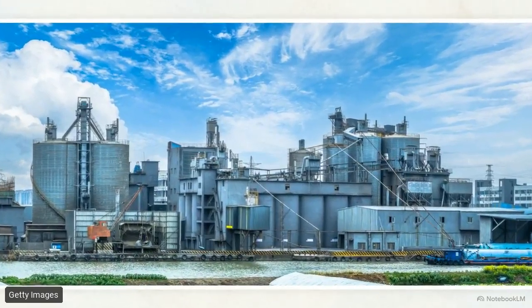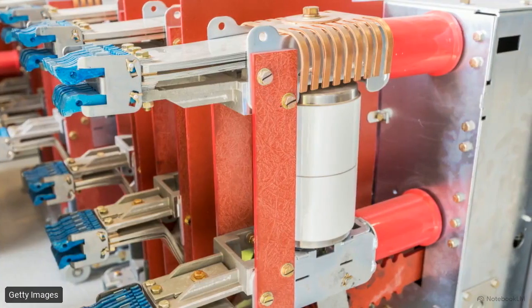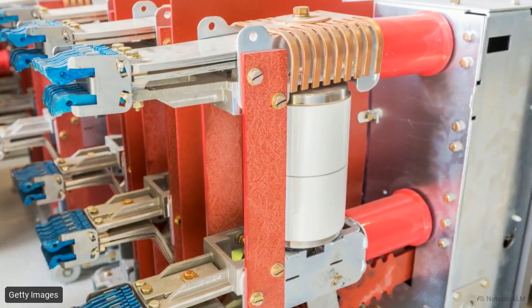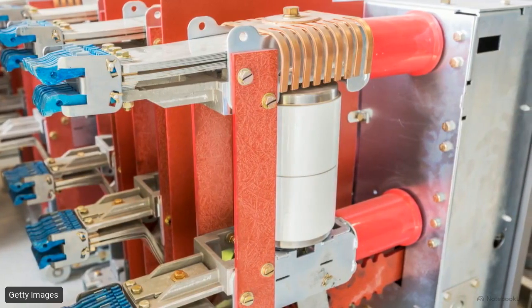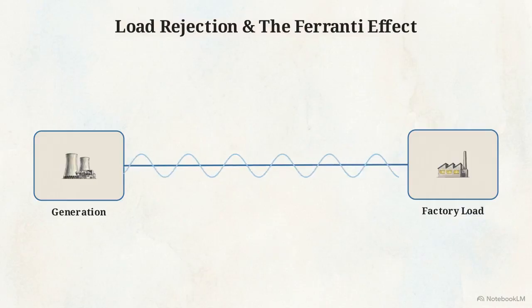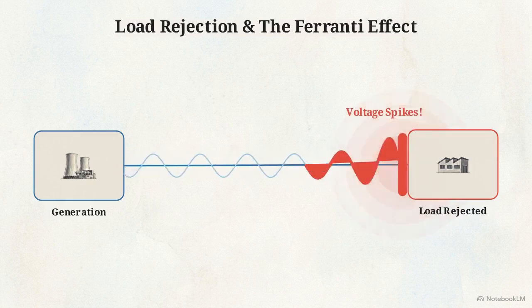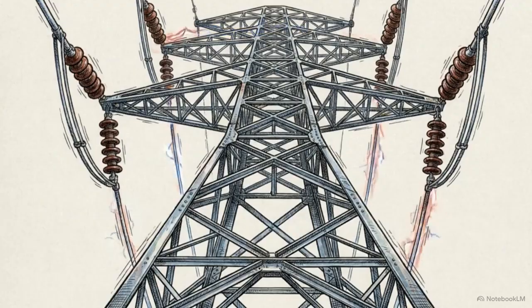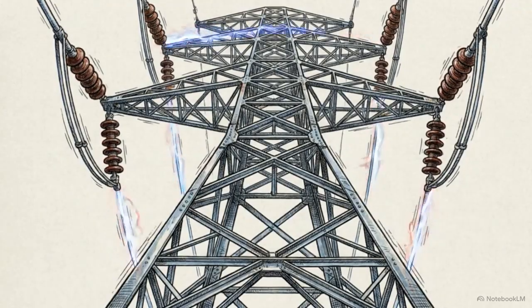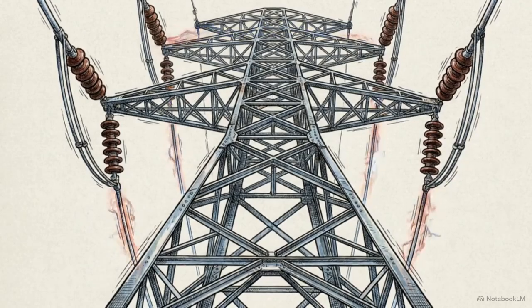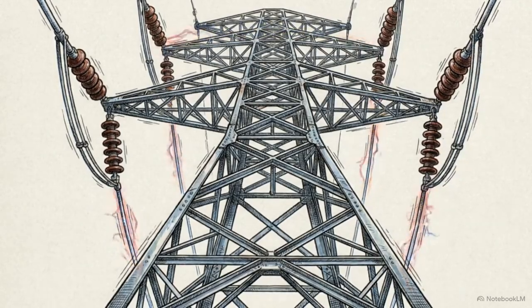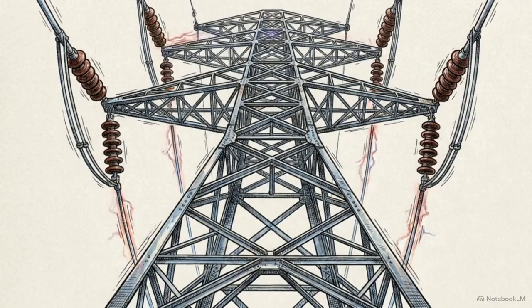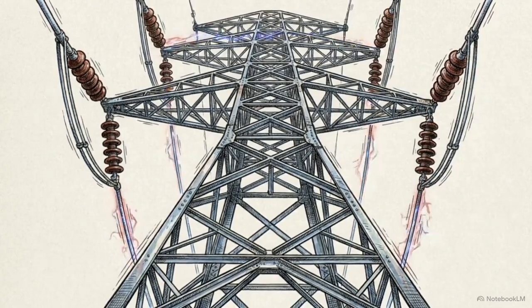During normal operation, a heavy draw from a factory consumes the stored energy from the line's power reservoir, keeping the system balanced. When that massive electrical draw is suddenly disconnected, engineers call the event load rejection. Without a destination drawing the power, the continuous flow of alternating current, or AC, hits an abrupt bottleneck at the end of the line. This load rejection traps the generating plant's raw energy inside our giant, sky-high reservoir, creating a highly volatile environment within the transmission line.